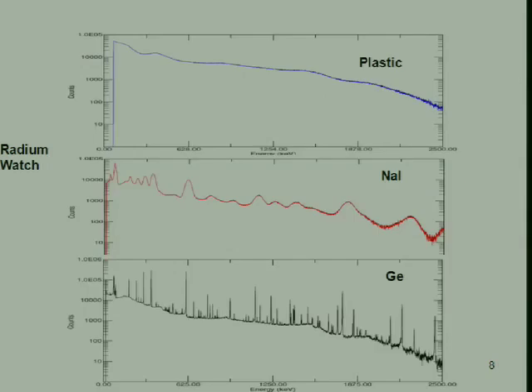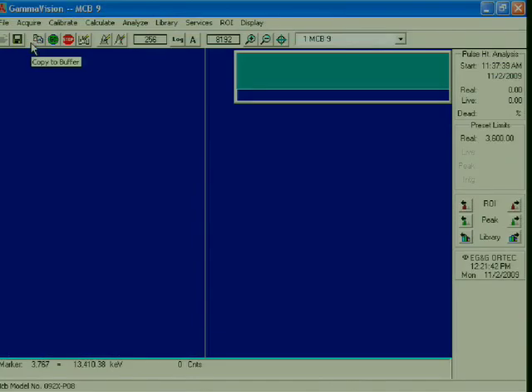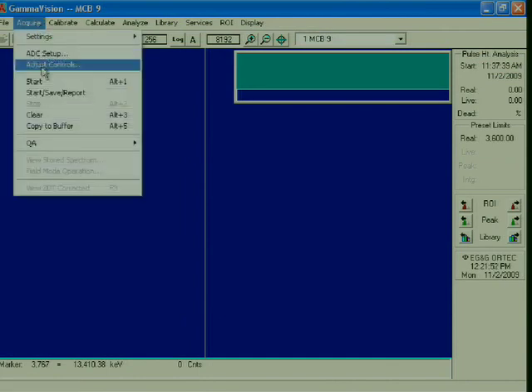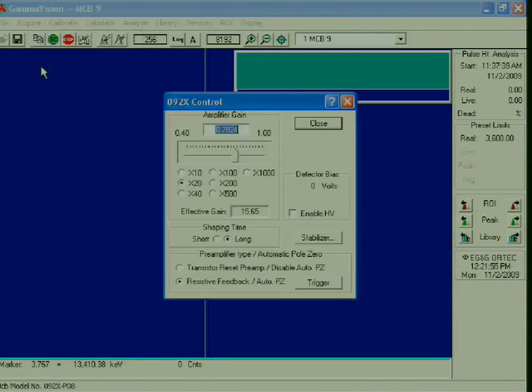Okay, so let me actually demonstrate this and show you that it really does work as advertised. So it's the same data acquisition system we had the other day. What I have to do is, again, to deplete the active region here, I have to apply about 3,200 volts across the crystal. And so we can do that. Adjust the controls. This lets me turn on the high voltage, and you can watch the voltage go up there. I have to be a little bit careful not to turn it up too fast. Essentially, you get sparks, and you can permanently damage the crystal or the electronics, and so you have to go up rather slowly.